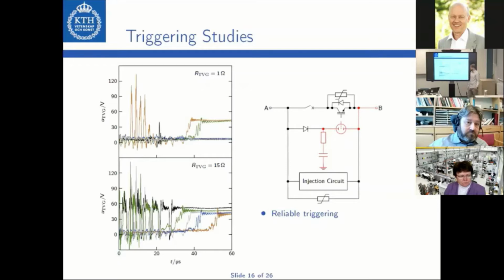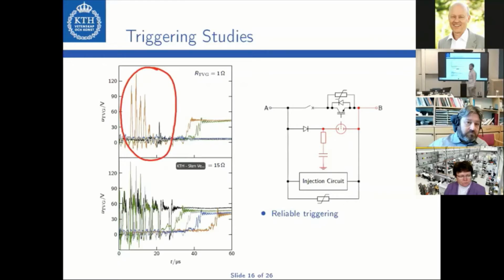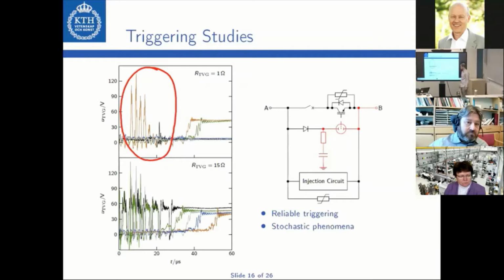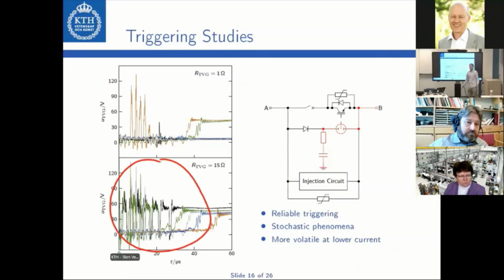This just demonstrates how stochastic the behavior of the arc discharge inside of the triggered vacuum gap is. Another aspect is that it is possible that high amplitude oscillations occur in the discharge voltage. The thing is that these kinds of oscillations and the volatility of the discharge increase at lower current levels. This you can see for the higher resistor value, where the oscillations can basically be observed at any time, and they also always occurred. The thing is, though, that the device still triggered successfully. However, the oscillation can cause the discharge to extinguish prematurely.